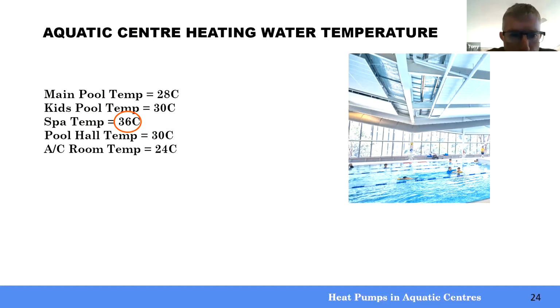But my point here is that if you didn't have the spa there, you wouldn't need to have 36-degree water. You could do it with 33-degree water, and that would be enough to heat your whole aquatic centre. And as I explained before in the previous slide, with 2.5 to 3% per degree difference, we're looking at about a 15% additional energy consumption of the whole heating system of the whole aquatic centre, just because you have a spa. So we need to think about not everything when we're talking about using heat pumps in an aquatic centre, how we're designing everything associated with that.